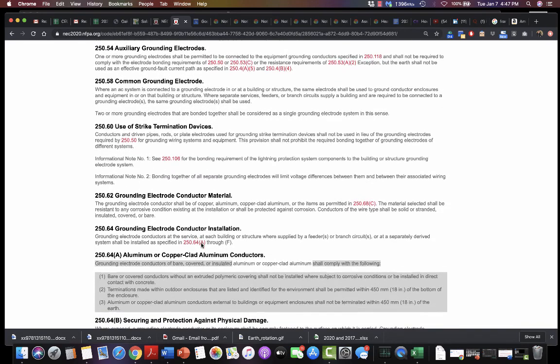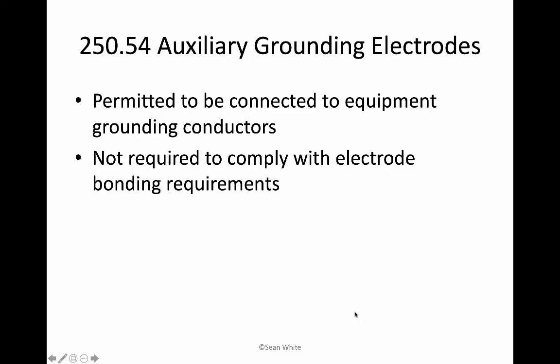250.54, and that is auxiliary grounding electrodes. And we argue about that over and over in 690 throughout the years. And these auxiliary grounding electrode conductors are permitted to be connected to equipment grounding conductors. Some people don't like that. It's like off the roof of your PV system, you just hook up to the rail or something and then bring it down to the ground. It's almost like that. Or your equipment grounding conductor up on the roof, bringing it down to the ground.